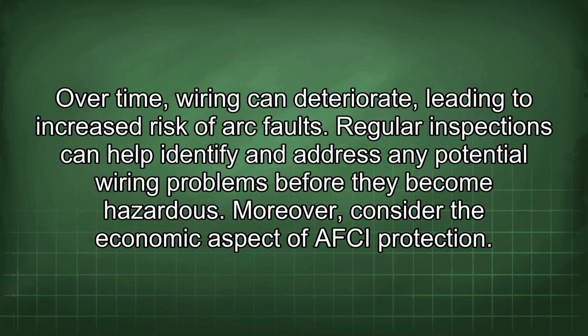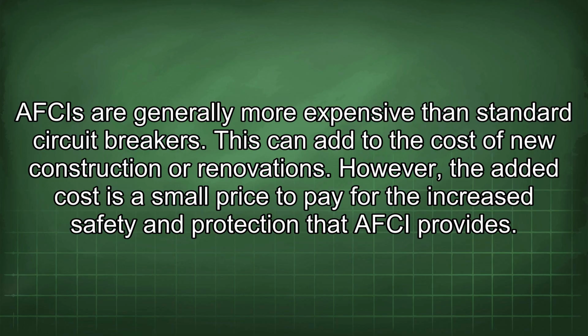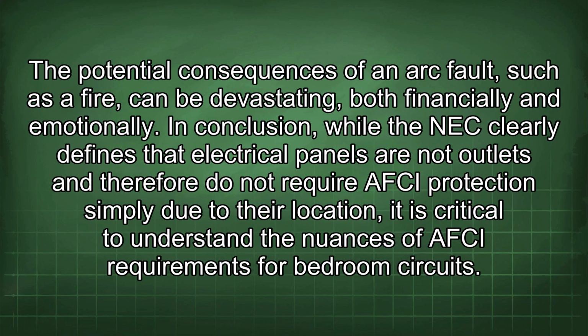Moreover, consider the economic aspect of AFCI protection. AFCIs are generally more expensive than standard circuit breakers. This can add to the cost of new construction or renovations. However, the added cost is a small price to pay for the increased safety and protection that AFCI provides. The potential consequences of an arc fault, such as a fire, can be devastating, both financially and emotionally.